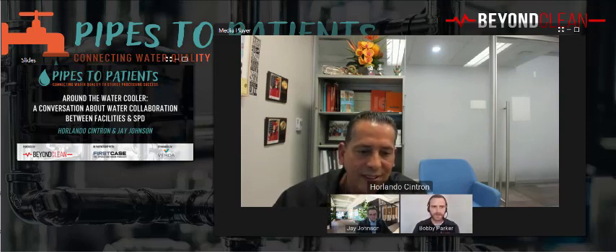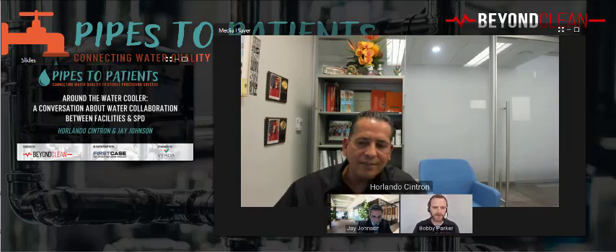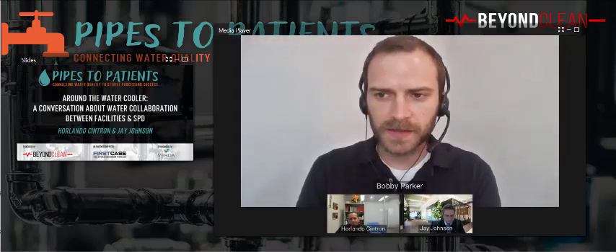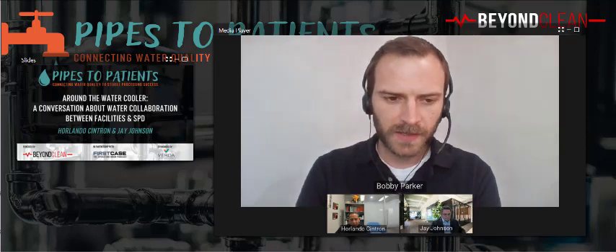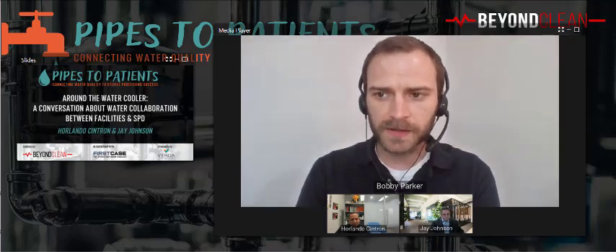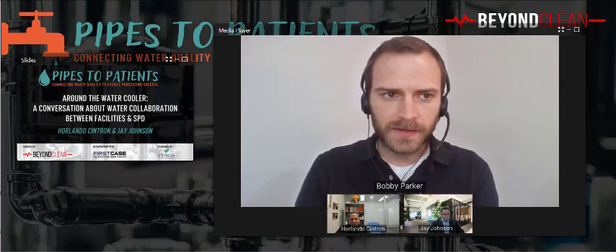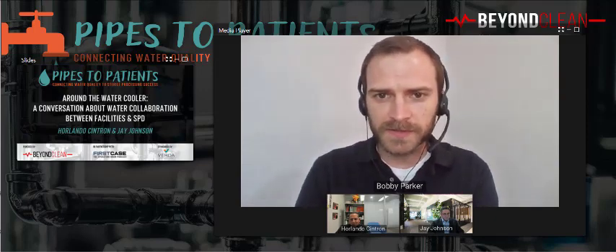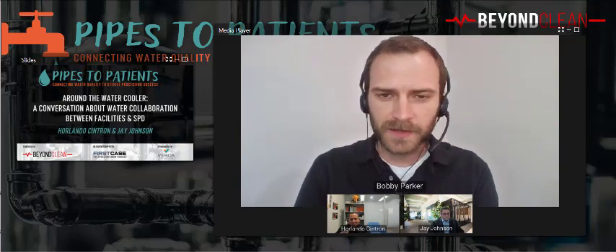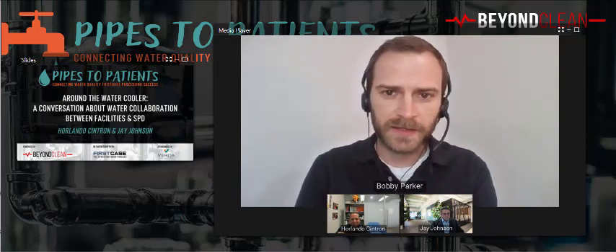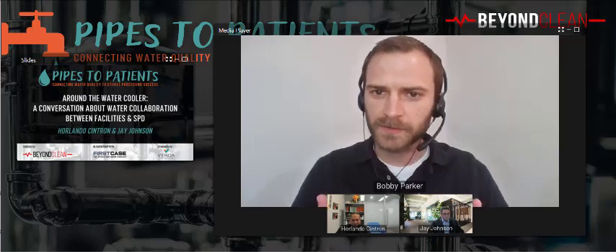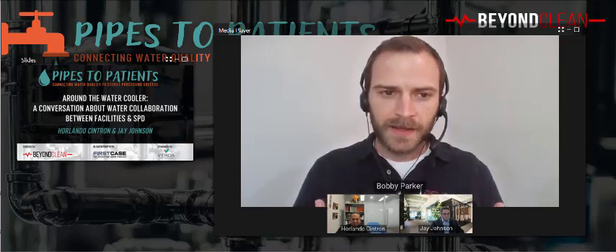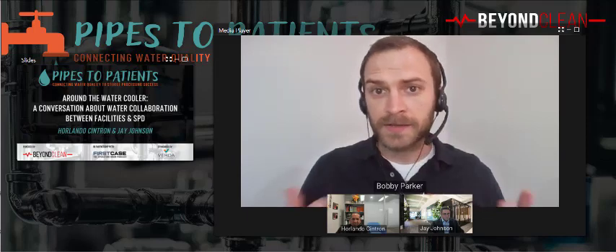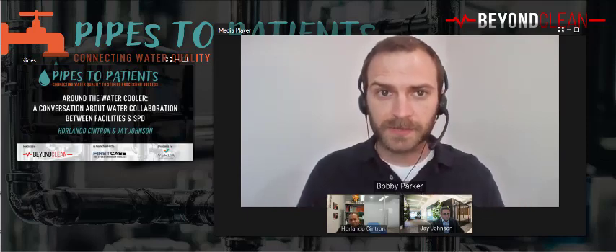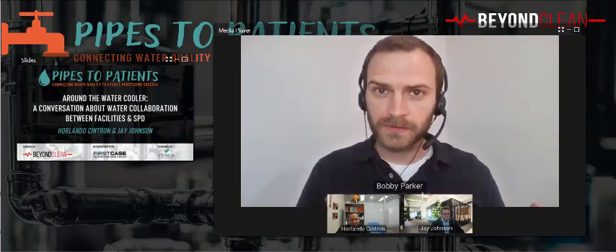Thanks for sharing that insight. It definitely is complex. I think you're right to be questioning that critical rinse at the end, because that is what should be preventing a lot of the staining and water spotting. Rusting, believe it or not, is most likely to happen on a brand new instrument. As instruments are manufactured, they go through a passivation process where an oxide layer is built up on the outside of the instrument and iron particles are removed from it. That process happens naturally, just with stainless steel. It naturally builds up that passivation layer. They try to accelerate it in the manufacturing process by putting it through an acidic bath.